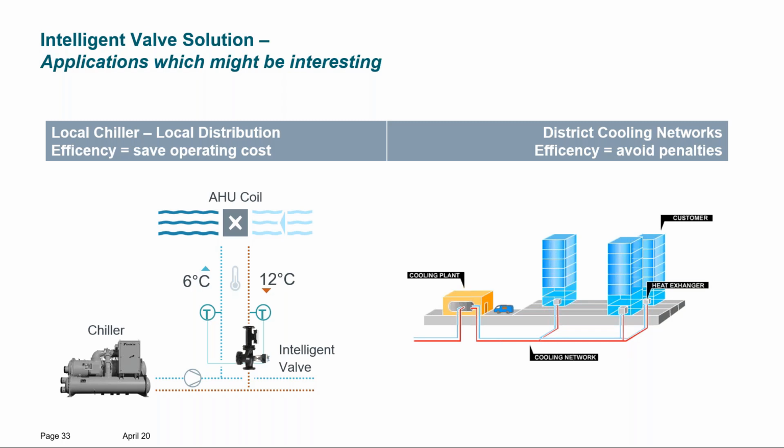Let's imagine you don't have a dedicated chiller plant for the building, but the buildings are connected to a district cooling network. There you usually have contracted not only a certain power capacity you are allowed to consume as a user. You have also usually contracted to maintain a certain delta T across the connection point and the district cooling substation you might have in the basement of the building.